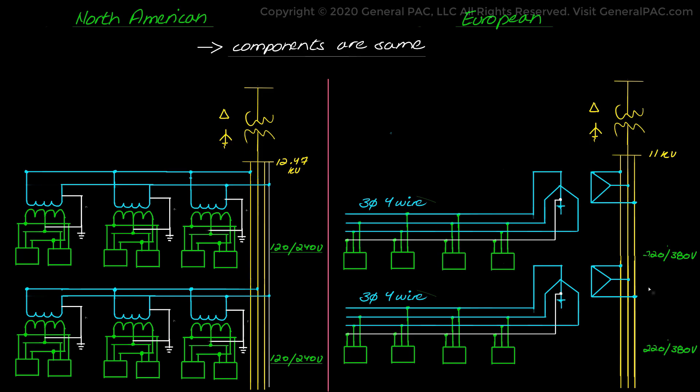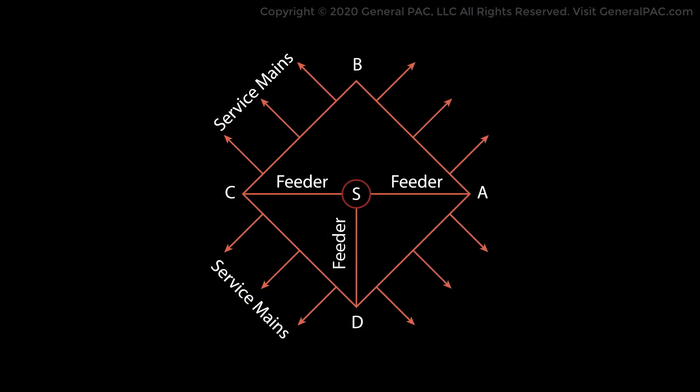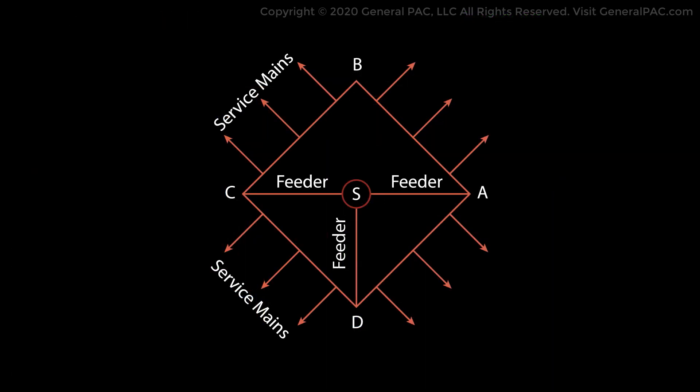Generally speaking, an electrical distribution system at the secondary stage consists of three distinguishable conductors: feeders, distributors, and service mains. A feeder, also called a mainline, is the backbone of the distribution circuit which connects the substation or localized generating station to the area where power is to be distributed. Current remains the same throughout a feeder because it supplies current without being tapped at any intermediate point.